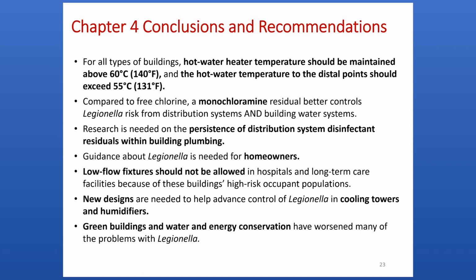Water conservation is a similar problem. As we conserve water, we reduce the flow inside the building. The water residence time goes up. Whatever disinfectant residual you might have had will dissipate. Whatever temperature control you might have had will go away, and suddenly the building plumbing is much more ripe for Legionella growth. So these buildings need to be redesigned and retrofitted so that these problems can be eliminated.